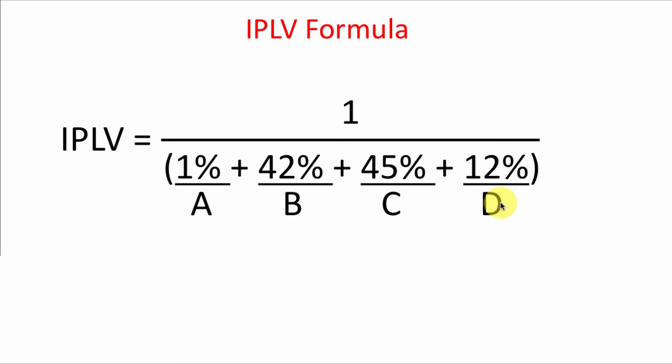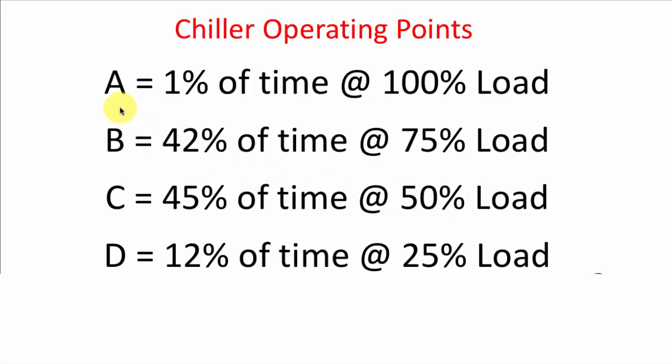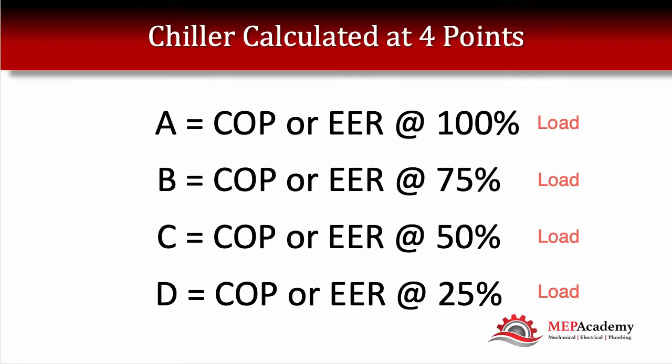So what are A, B, C, and D? The EER for these four points will be put into the calculation. A is 1% of the time, when the chiller is running at 100% load. B is 42% of the time at 75% load. C is 45% of the time at 50% load. And D is 12% of the time at 25% — quarter — load.